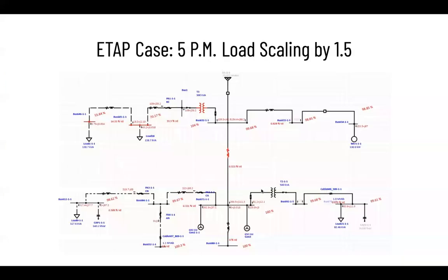Okay, this is also our same case hour, which is at 5 p.m. However, what we wanted to do here is scale up our load by 1.5. The reason we wanted to do this is to determine if our system would need an upgrade. We wanted to see if our conductors can hold what our voltage and generation sources are delivering to our loads.